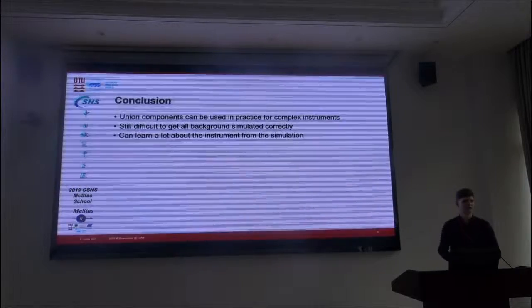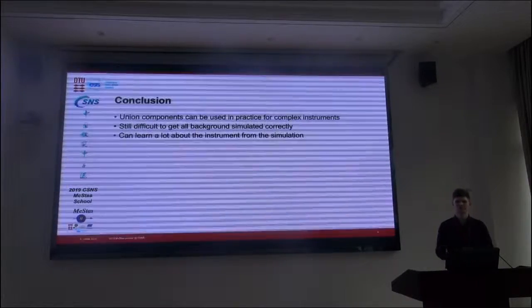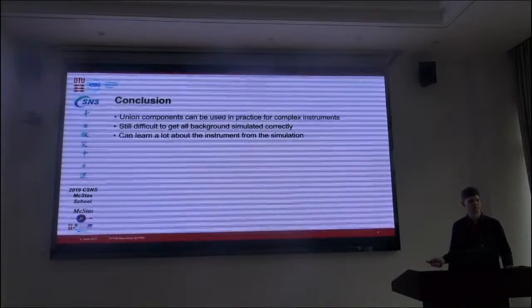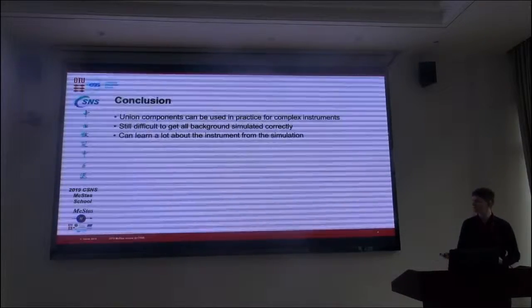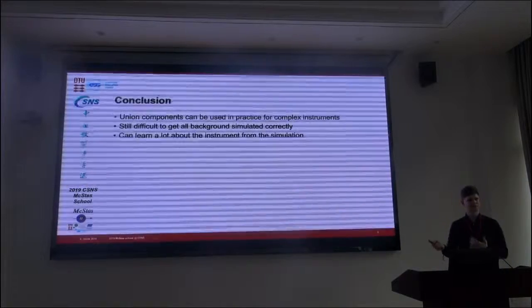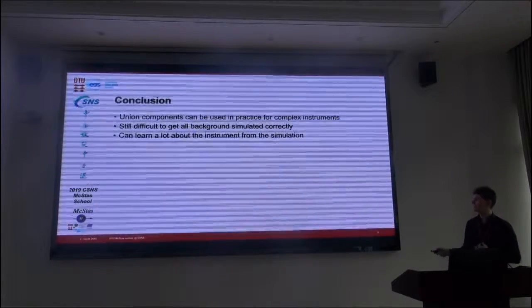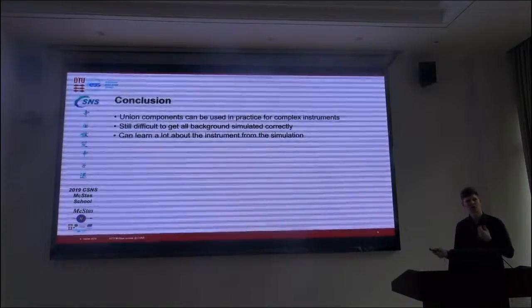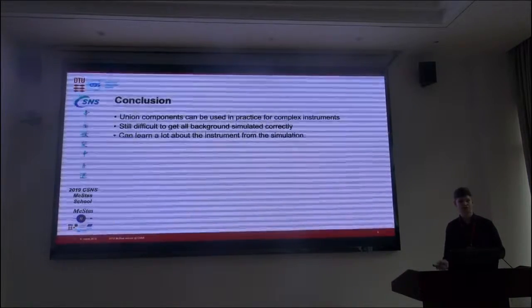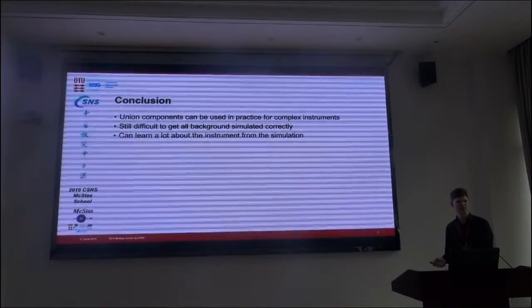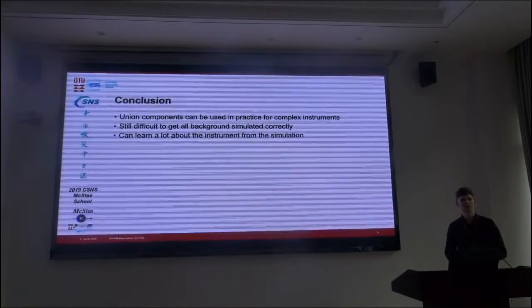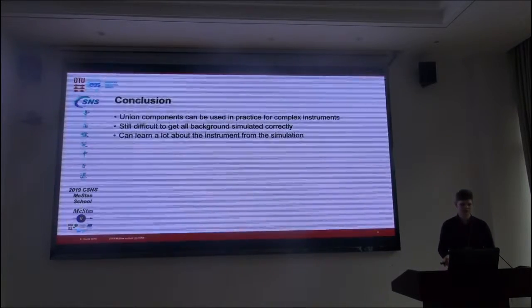That was just a quick demonstration of how far you can push this set of components. I am showing that it can be used for practical purposes. It will take a larger computer than a laptop, but you can do it. It is very difficult to get background simulated correctly, but at least there is a tool to make the attempt. I still think even if you don't get it perfect, you can learn a lot about what goes on on an instrument. For example, they would rather have chosen a different shielding material because they would have gotten less albedo scattering with a lower scattering cross section. There are things to learn and understand by doing simulation, and I think these components can really help you with that.